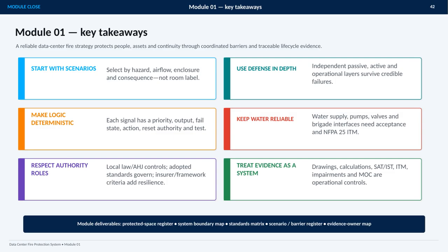Start with scenarios, not room labels. Select the protection approach based on the hazard, airflow, enclosure, and consequence, so the design reflects how a fire could actually develop. Next, use defense in depth. Independent passive, active, and operational layers should continue to provide protection even when a credible failure occurs.